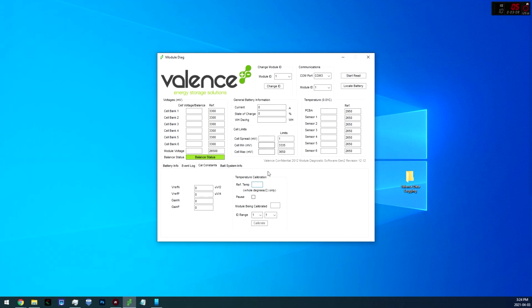Then you go from the ID range, whatever your batteries are. So if you have 20 batteries and the ID range is from 1 to 20, you would go from 1 to 20. After that, you would start reading on whatever COM port it is, and you'd be able to calibrate all of them.